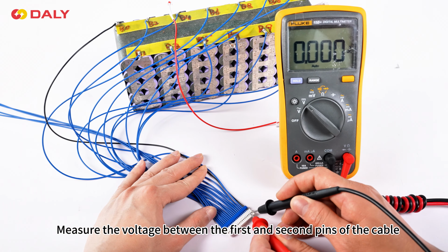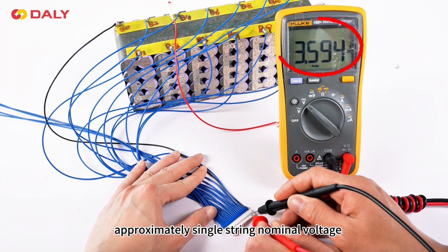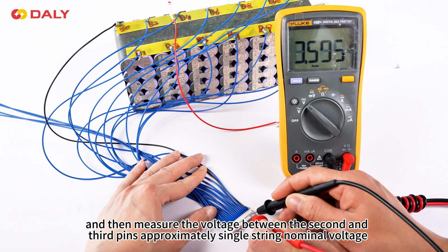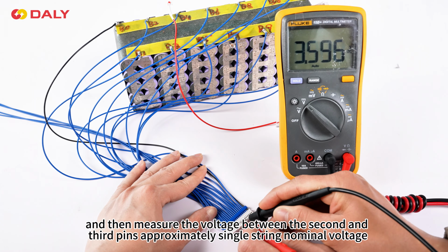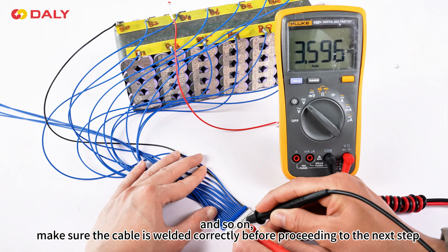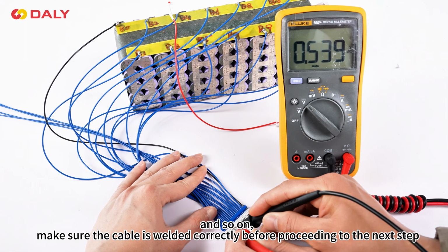Measure the voltage between the first and second pins of the cable, which should be approximately the single-string nominal voltage. Then measure the voltage between the second and third pins, again approximately the single-string nominal voltage, and so on. Make sure the cable is welded correctly before proceeding to the next step.